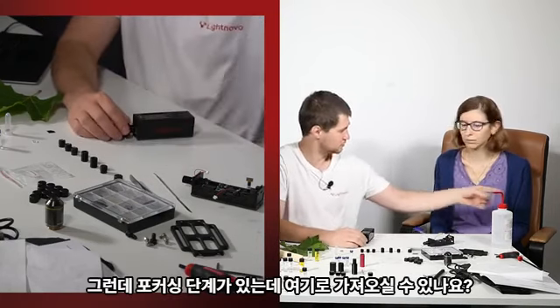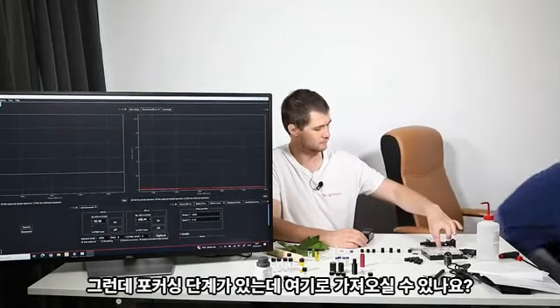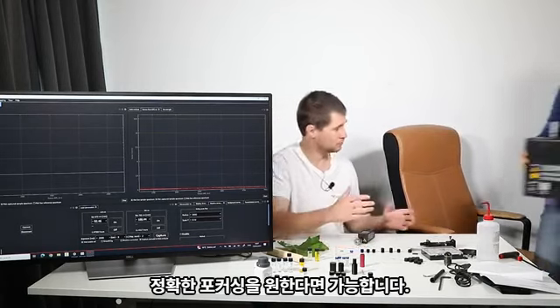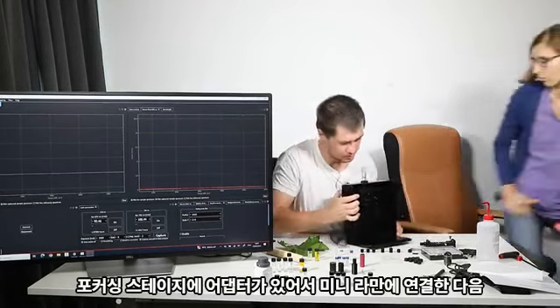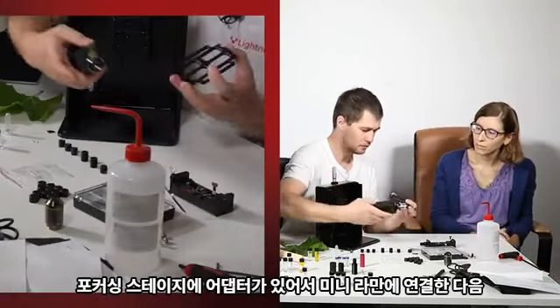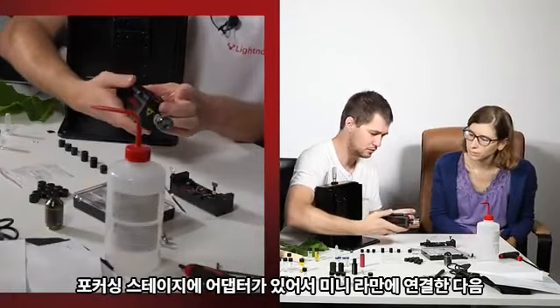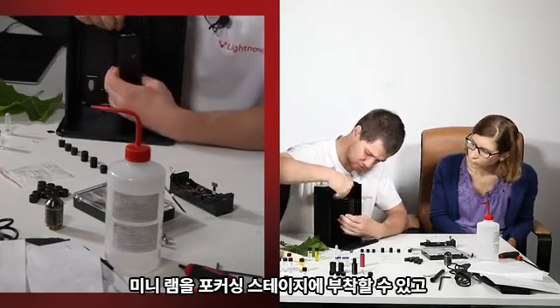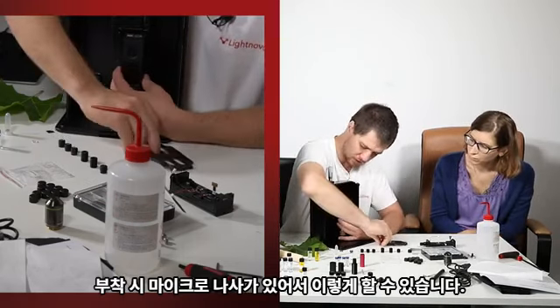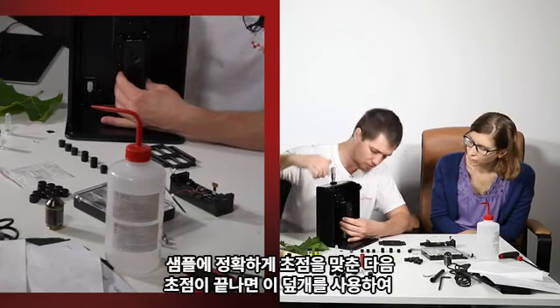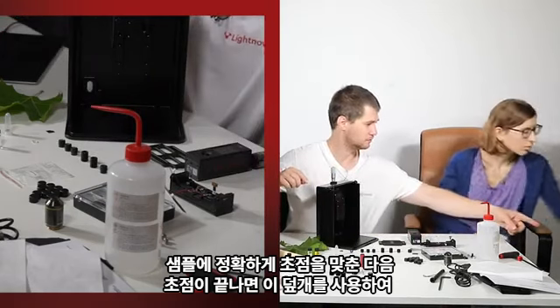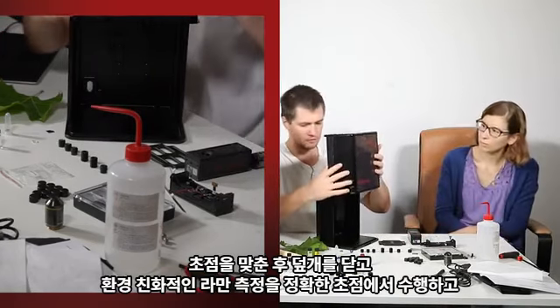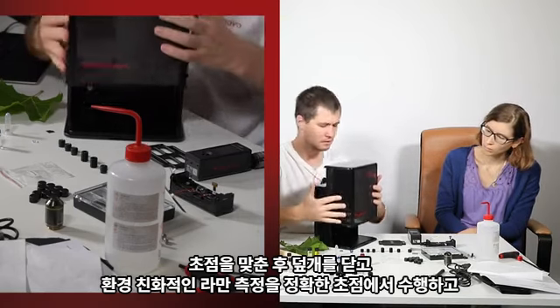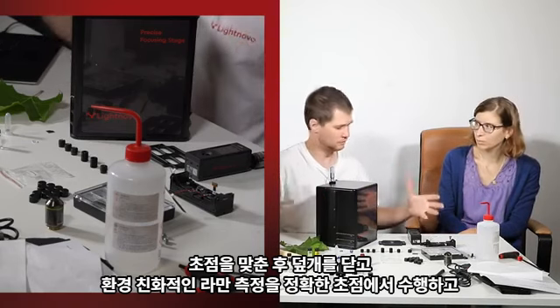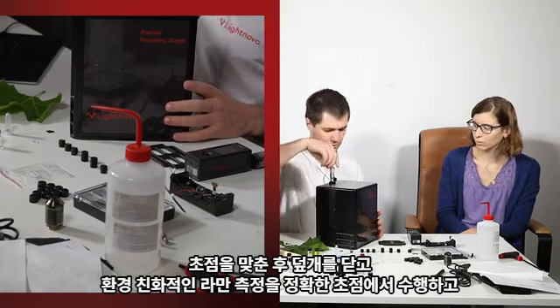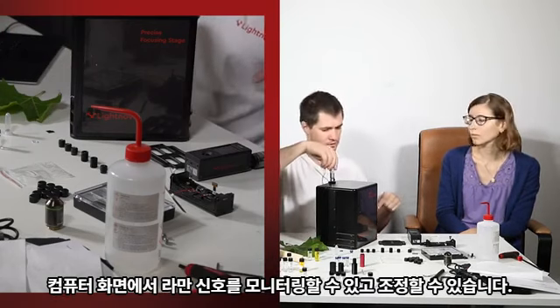And by the way, there is a focusing stage. Could you just bring it here? I will show what can be done if you want precise focusing. Yes, great. So with the focusing stage, we have an adapter. You connect it to the miniRaman, and then you can attach miniRaman to the focusing stage, and when attached, it has a micro screw. So you can focus on your sample precisely, and then with this cover, when you are done with the focusing, you can close it and do environmental free Raman measurements at precise focus, and you monitor the Raman signal on a computer screen, so you can adjust it.